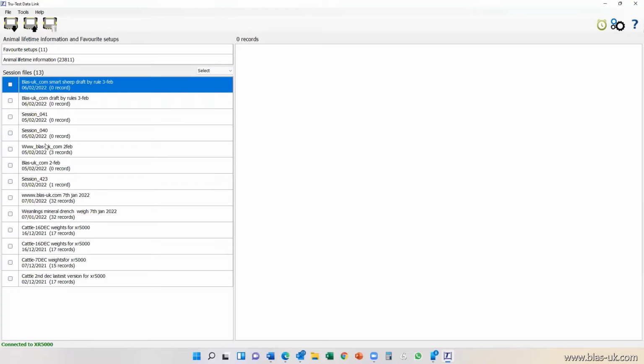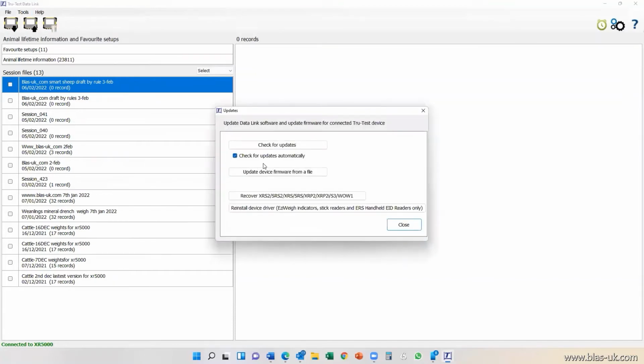To update the firmware or software on your Link software or on your TrueTest device, we need to go to Tools, Updates. We can either set this to automatically check for updates every time you connect your TrueTest device, or you can have it on manual. By having it on manual, this is preferential for some of the third-party management software that have an automatic download capability of downloading off a TrueTest device into their own management software.